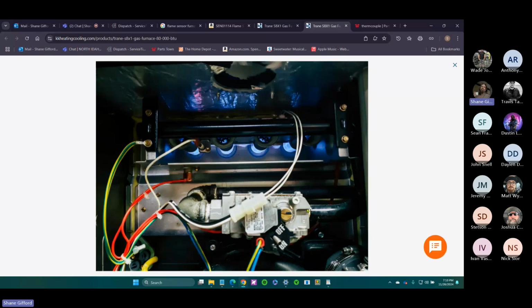If you lose your blower motor, you don't want to keep your burners going, because you're going to overheat and melt your heat exchanger. Normally they're rated like 250 degrees, 275 degrees. So you do have a sensor in there by the heat exchanger or by the blower. We're doing York package units, gas packs, up in Bonners Ferry. Those are York, so they've got their pressure switches, but they put their high limit switch right beside the blower after the heat exchanger, right down in the airstream. So it's close enough to the burner that it's not going to naturally overheat and shut off. It wants it close enough that if we lose blower, it's going to overheat very fast and shut down.